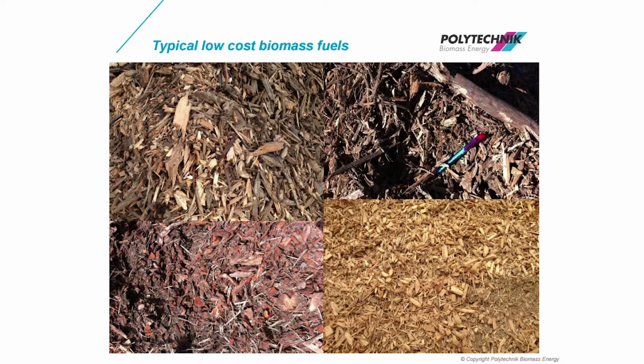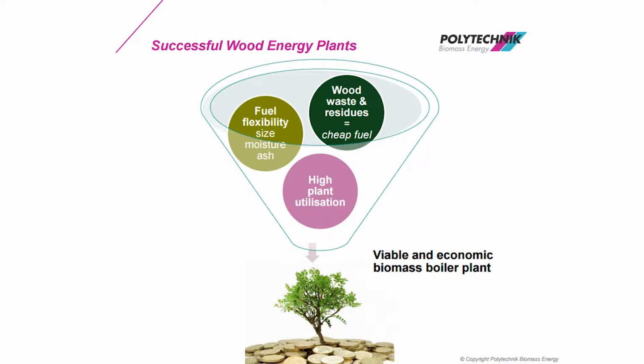This is just a photo of the typical fuel streams that the boiler plant's running on. So we've got bark and hog fuel. I class them as a lower cost fuel. It's not a high quality wood chip. Quite a high moisture content. What Christian's trying to illustrate here is the diversity, I guess, of a well-designed boiler plant being able to handle varying fuels of varying calorific value and moisture content, and a high utilisation of the plant.